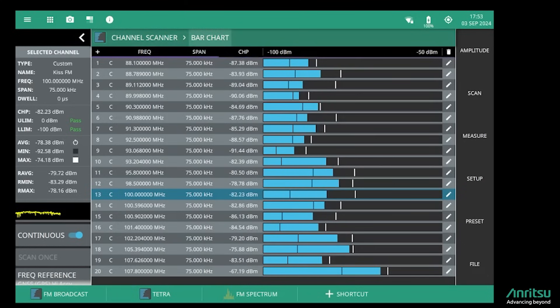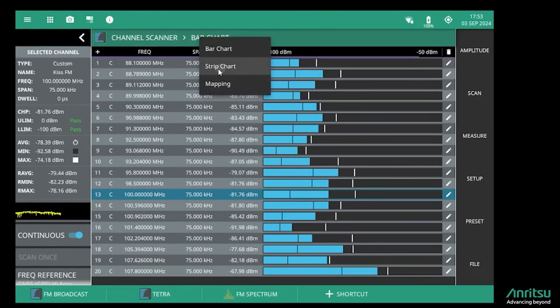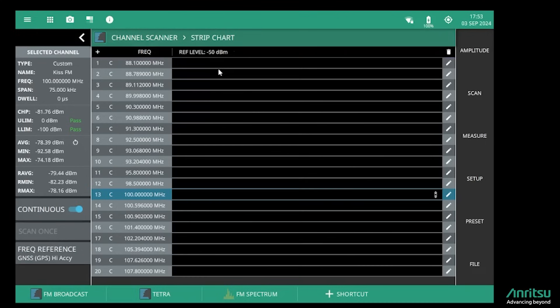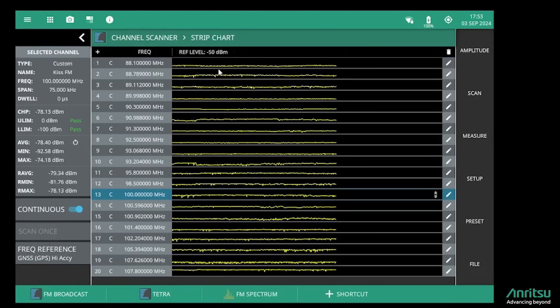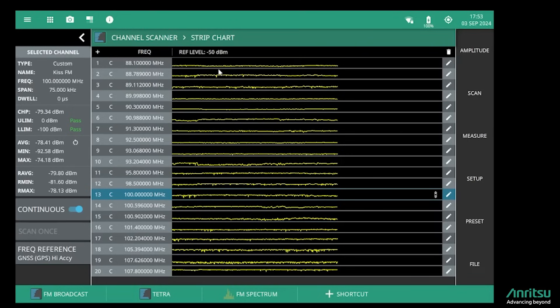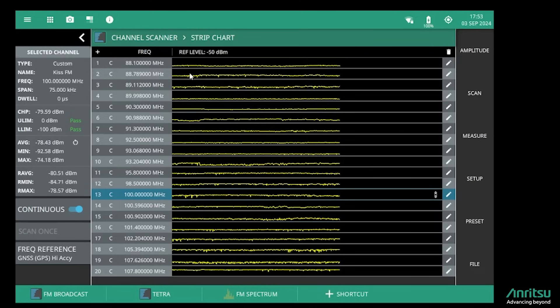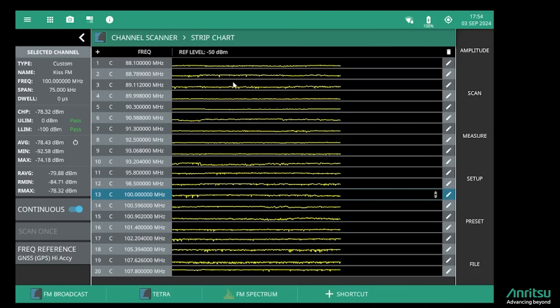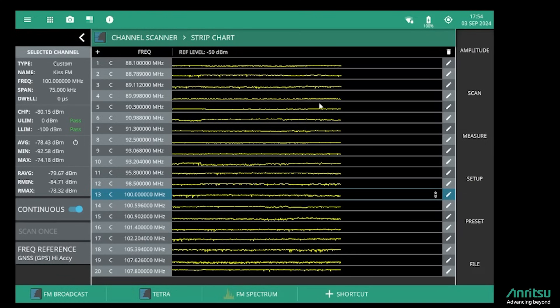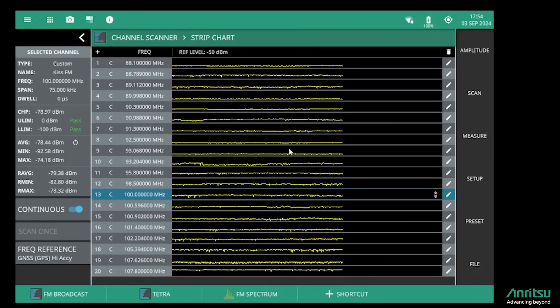I can also switch from a bar chart mode to a strip chart mode. In the strip chart mode we have a thousand data points, so that's about 15 minutes worth of data at this update rate, and we can monitor the change in level of any individual channel over a period of time.